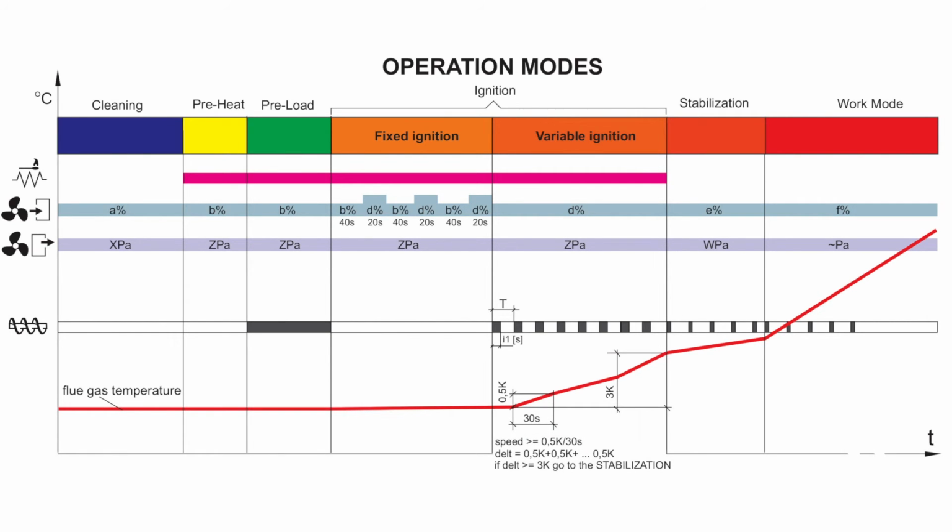The boiler operates on PID modulation, so will modulate freely between 30% and 100% of boiler output. Once it reaches the target temperature, it will continue to run at its lowest power for an extra 5 degrees Celsius temperature rise before going to the burning off extinguishing stage. Burning off lasts for a minimum of 7 minutes.